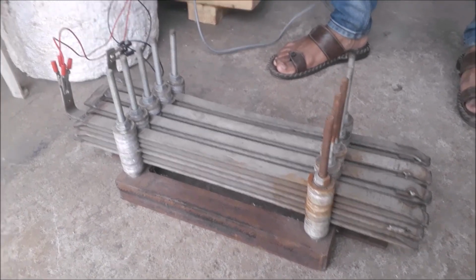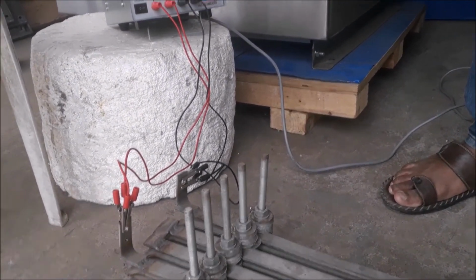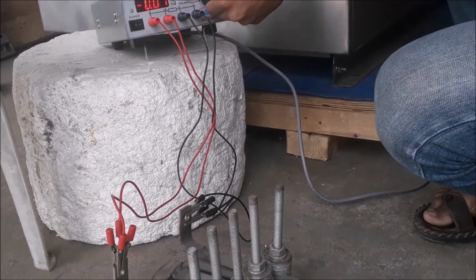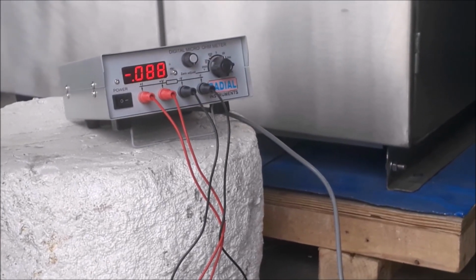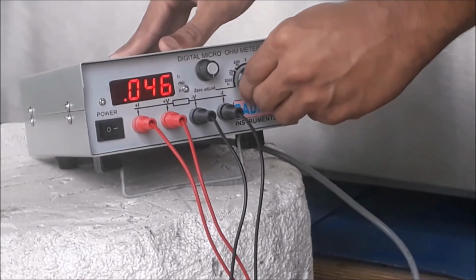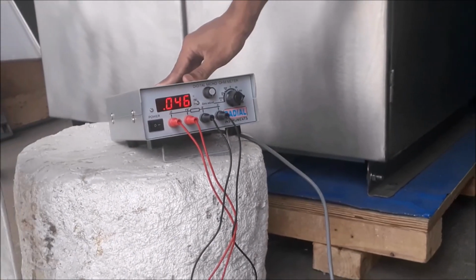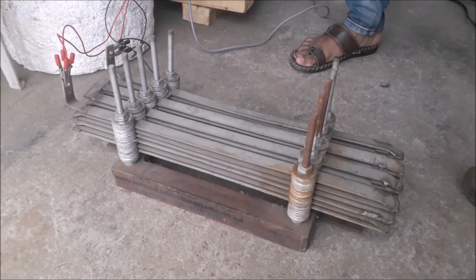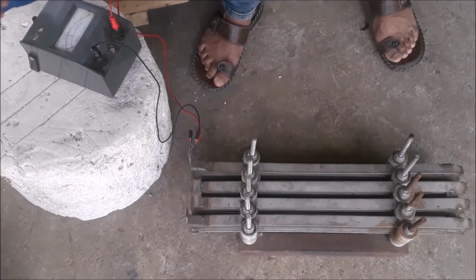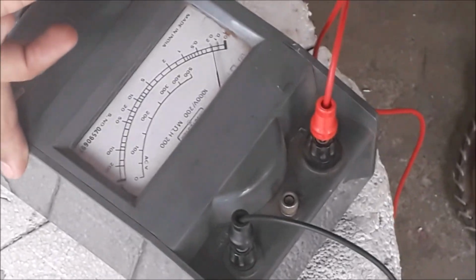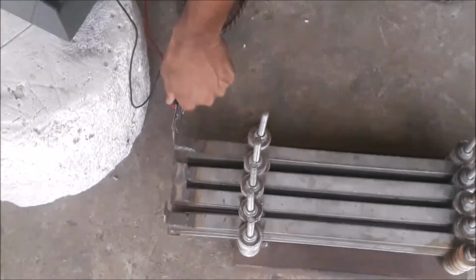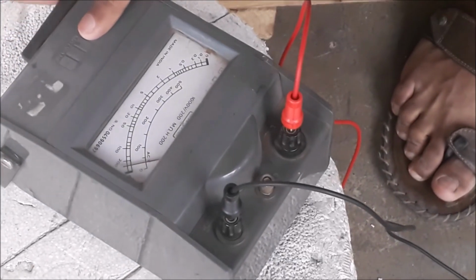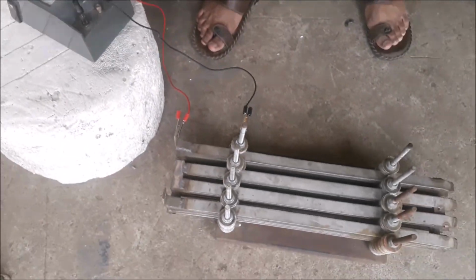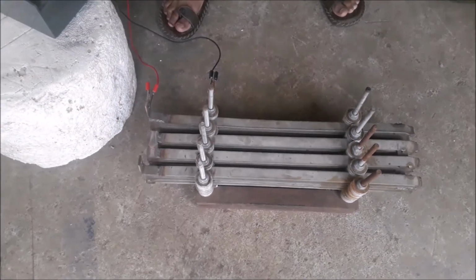In the resistance measurement test, we measure the resistance of our prototype with the help of a digital ohm meter by passing DC current through it. In a Megger test, we give a high DC voltage with the help of a Megger and check the resistance between terminals and enclosure. The resistance between terminals is near to low or zero, and the resistance between terminal and bracket is infinity.